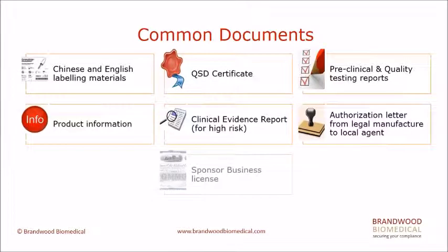There are some common documents for registered products for Class 2 and 3 devices in Taiwan. The Chinese and English labeling materials. Taiwan is very particular on the instruction for use and labels. I will walk through TFDA's key labeling requirements in the next slides. And the QSD certificate is required for devices above Class 1. And again, we'll go into details in the next slide.